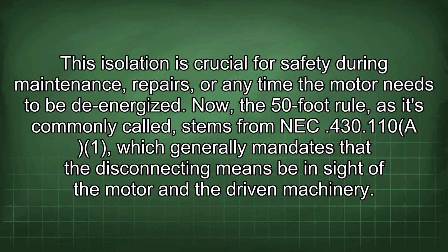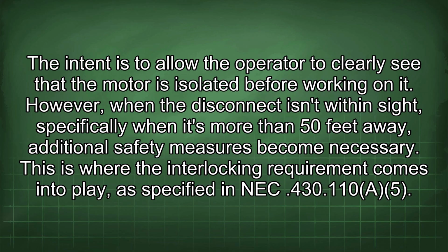Now, the 50-foot rule, as it's commonly called, stems from NEC 430.110 which generally mandates that the disconnecting means be in sight of the motor and the driven machinery. The intent is to allow the operator to clearly see that the motor is isolated before working on it. However, when the disconnect isn't within sight, specifically when it's more than 50 feet away, additional safety measures become necessary.